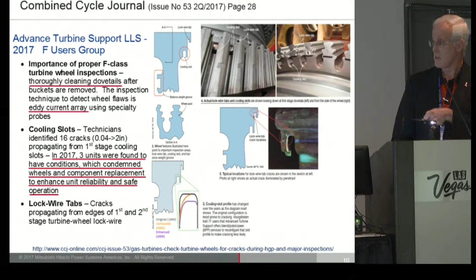Even in 2017, three more units were found with significant cracks developing on the rotor discs, due to the characteristics of the Inconel and the way it more easily initiates and propagates cracking. On this graphic, the first line, the black line, is the original design from '95. The first red one talks about a fix that came up in 2002, and then in 2005 they came in with that purplish line that finally fixed this problem in the groove that was having significant crack issues.